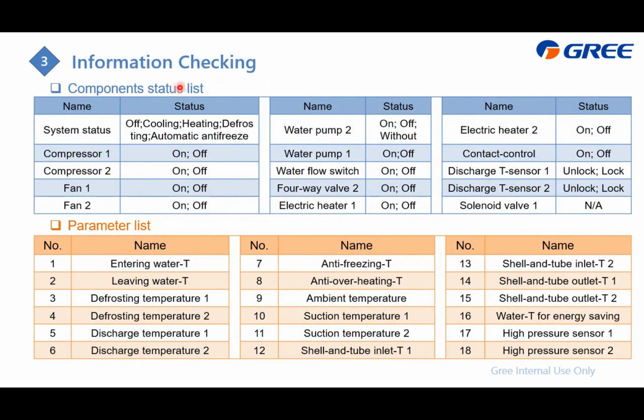Here is the detail. First is the component status. We display all the parameters, either on or off, including the compressor, fan, water pump, water flow switch, 4-way valve, and e-heater, and also the contact control, whether it is on or off, and also the discharge sensor and the solenoid valve. And as for the parameter, we will show you all the sensor detected values.